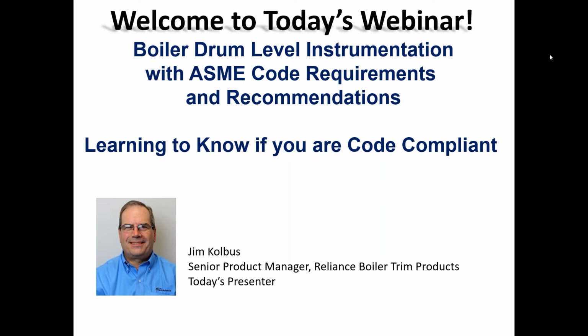Today, Jim will be going over the ASME boiler and vessel code details. He will show illustrations of common code violations and how to fix them, and explain the limitations for various types of direct and remote level indicator technologies. In this session, he will highlight water gauge glasses and remote level indicators, ASME Section 1 requirements for water level instruments for steam power boilers operating in excess of 15 psi. He will also talk about isolation and drain valve concerns and recommendations. He'll talk about the CSD1 requirements for low water cutoff devices, recommended blowdown procedure for level instruments, and of course, answer any questions you have along the way.